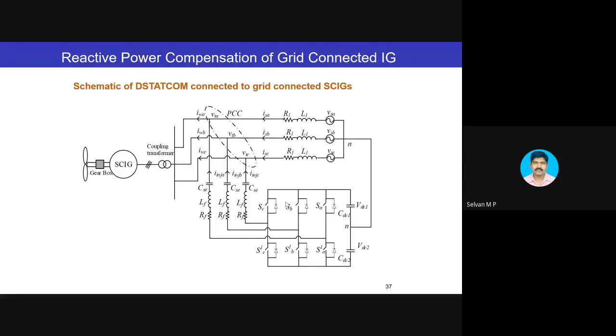So they are asked to have their own reactive power compensating devices. Mostly they go for capacitor based reactive power compensating devices, which will not be able to provide dynamic reactive power compensation. So this is where we can go for STATCOM. It need not be connected to a single machine. You can connect it to a number of machines connected together. I mean, for a single wind farm, we can have a STATCOM.